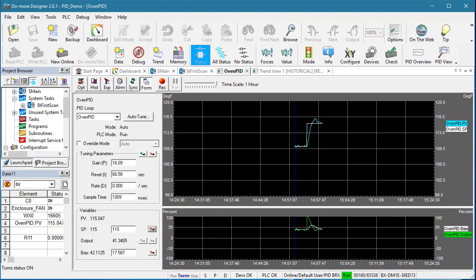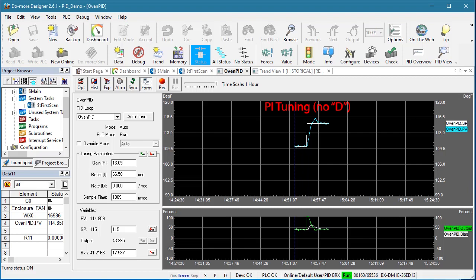That took a few minutes and the Do-more engine automatically adjusted the PID output to get us to the new set point quickly and efficiently. Exactly what we expect. You can see where it's constantly adjusting things to maintain that 115 degrees. And these variations are just a fraction of a degree.